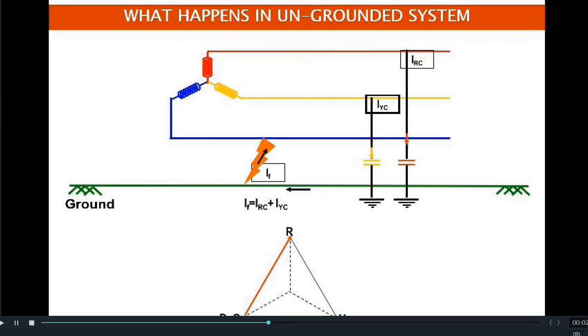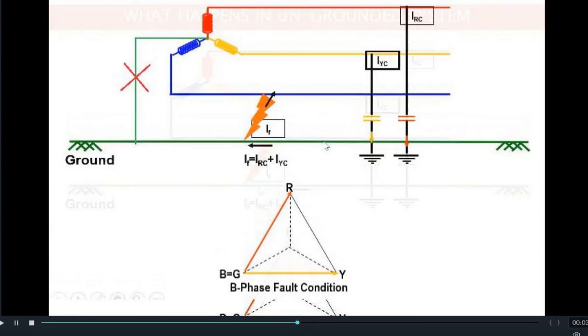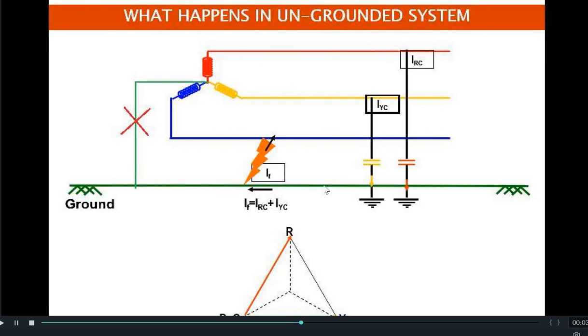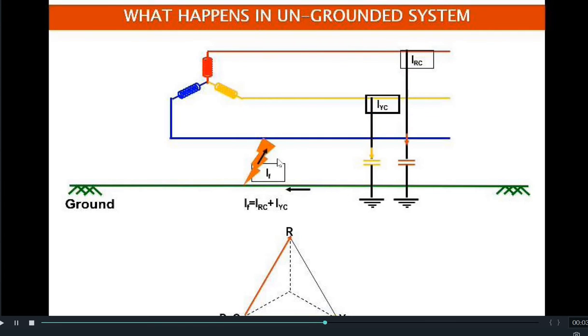The house appliances connected from phase to neutral will face a phase-to-phase voltage because of this ground fault. The currents from R phase and Y phase — IRC and IYC — will still flow to the ground and finally to their source through the faulty B phase. As there is no connection between the neutral and the ground, there will be negligible fault current from B phase, making it very difficult to distinguish the fault. Additionally, due to the capacitive effect there will be arcing grounds or restriking voltage, as the capacitors charge and discharge repeatedly.